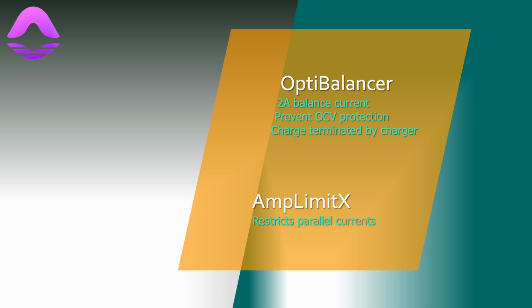The OptiBalancer is a cell balancing circuit that can deliver a balancing current of 2 to 2.5 amps. It effectively balances the batteries, particularly for large capacity batteries. Importantly, it prevents the battery from triggering OCV protection, ensuring that the charging cycle is ended by the charger rather than the PCM.